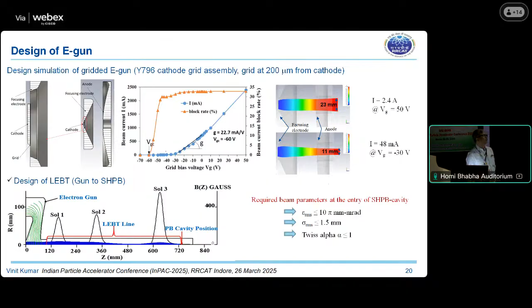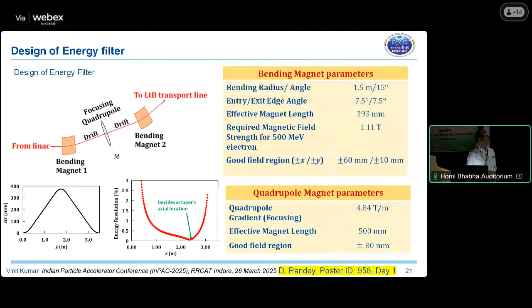The energy filter will have two 15-degree bending magnets which will bend the beam, and the important thing here is to achieve good resolution, because if you are aiming for 0.5%, the resolution should be something like 0.1%. That has been achieved, and there is a poster by Divyans who has done this design, so we can go through that.